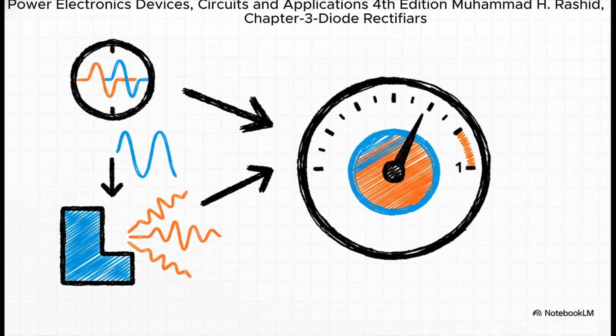And this is the main thing I want you to take away today: the overall power factor isn't just about that phase shift anymore. It's the product of both displacement and distortion. So if your current waveform is full of those nasty harmonics, your power factor gets hammered, even if the timing is absolutely perfect.